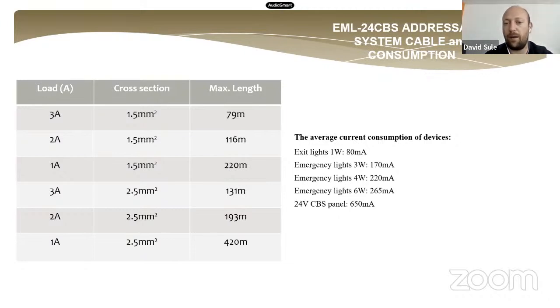One exit light current is around 80 milliamp. And here we can see the other emergency lights, 3, 4, and 6 watt types, and how much current. So the 6 watt is 265 milliamp. For example, we can take 20 pieces of exit lights into one circuit, so it will be 1.6 amp. Or we can take 12 pieces of 6 watt emergency light in one circuit, and we can mix the exit lights and the emergency light too in one circuit, because all of the exit lights and emergency lights have the same addressable driver inside.